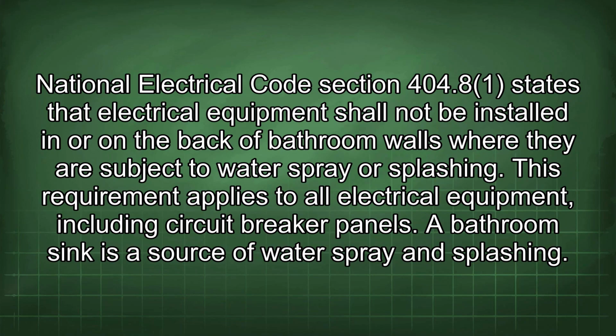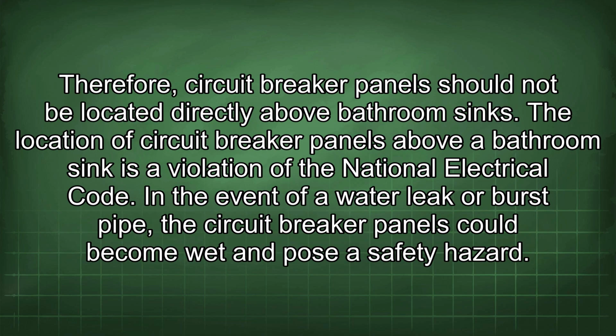National Electrical Code Section 404.8(1) states that electrical equipment shall not be installed in or on the back of bathroom walls where they are subject to water spray or splashing. This requirement applies to all electrical equipment, including circuit breaker panels. A bathroom sink is a source of water spray and splashing. Therefore, circuit breaker panels should not be located directly above bathroom sinks. The location of circuit breaker panels above a bathroom sink is a violation of the National Electrical Code.